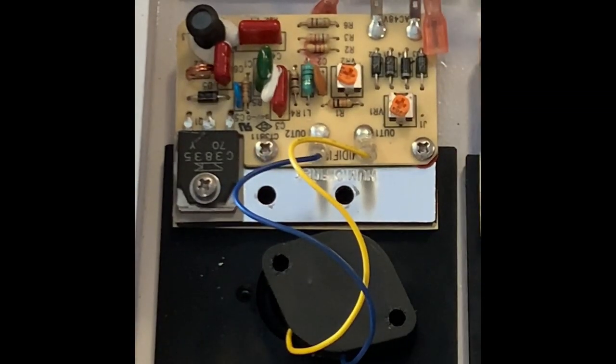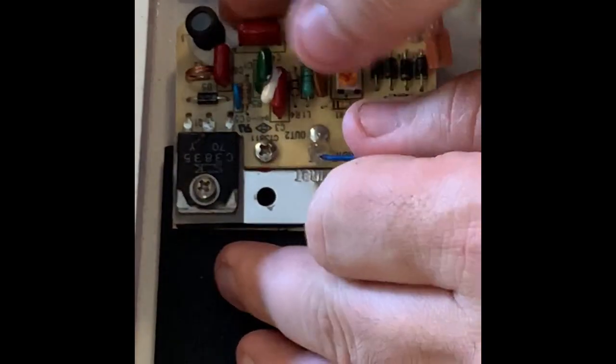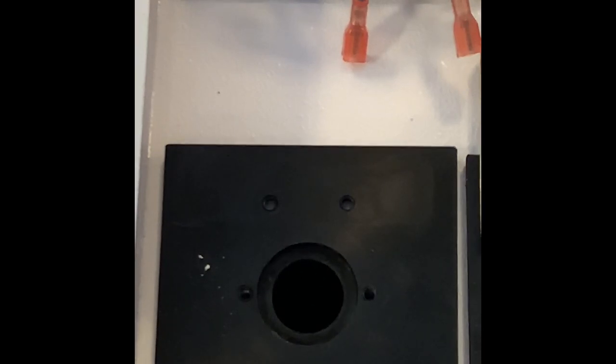Then you can remove the old circuit board. Remember, you will need to replace these as a set. The transducer and circuit board are paired together.